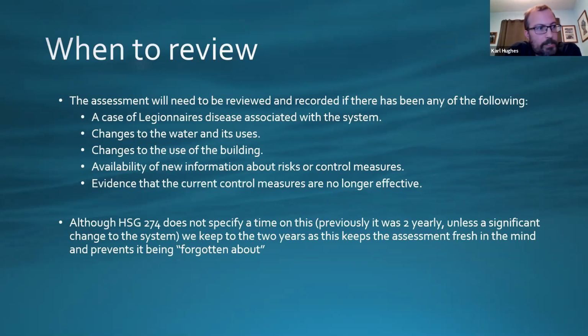So for example, in 2001, that's when the ACOP L8 came out. In 2013, 14, depending on whether it was part 1, part 2 or part 3, HSG 274 came out. So from then you would start recommending that new assessments be carried out to comply with HSG 274 as well. Or if there's evidence that the control measures in place are no longer effective. For example, if you're saying flush little used outlets on a weekly basis, and when you're still doing cold water storage or hot water temperatures, that they're failing. And one of the things it says in the new HSG 274 is, whereas previously it was every 2 years, unless any significant changes have been made to the system, for example, the ones above, we as a company still prefer to keep a 2-year review on that, because obviously it keeps it fresh in the person's mind, and it's constantly evolving and it's not being forgotten about.